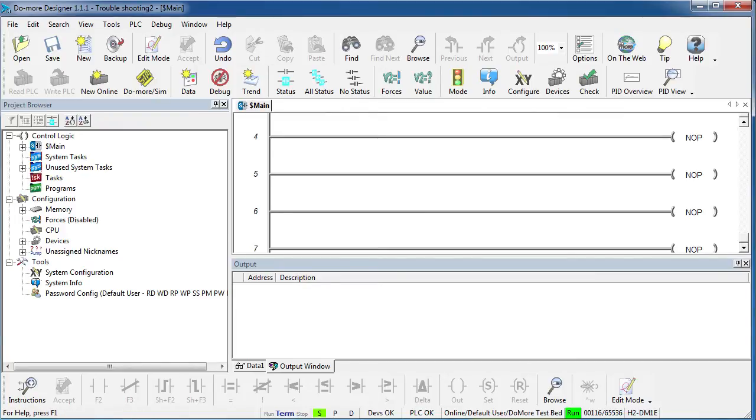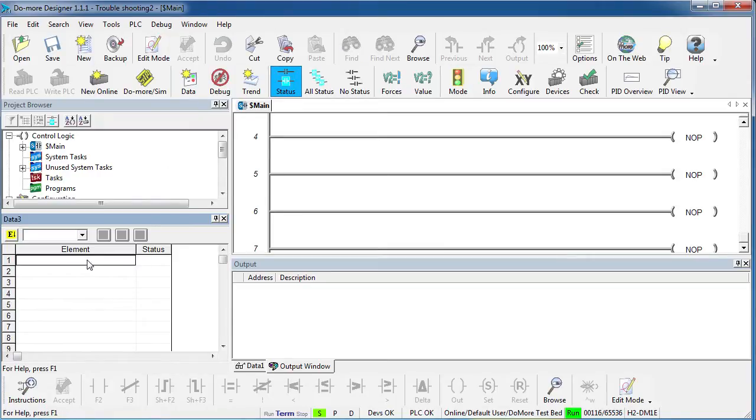check engine light, you can also do it programmatically. There's a new Ethernet master error flag that's basically the status of that check engine light. There's also this Ethernet I/O master structure which has this general error flag too. It's very similar to the Ethernet master error, but just to be sure I don't miss anything, I check both, and if either one's active, I then go ahead and launch some kind of Ethernet I/O diagnostic program.